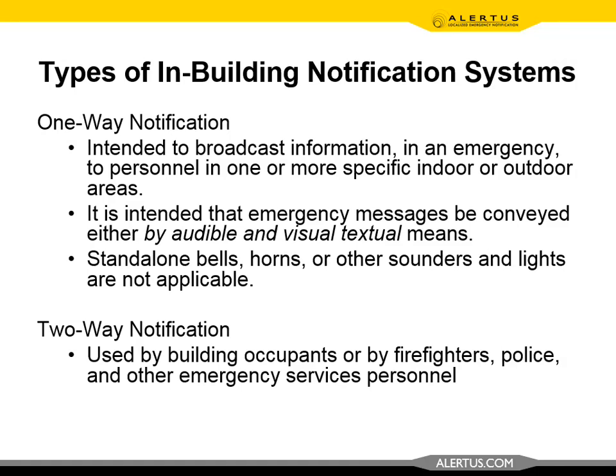But one-way is intended to broadcast information and emergency messages to personnel in one or more specific indoor or outdoor areas. It's intended that emergency messaging be conveyed either by audible or visual means. In fact, they look to have both of those to be compliant with the codes. And then standalone bells, horns, other sounders, lights, really aren't applicable.